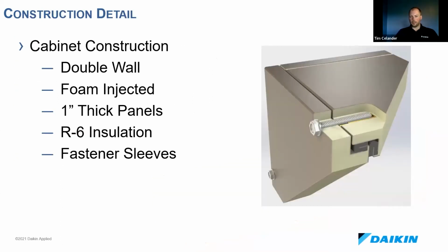So when I talk about that exciting cabinet, here's what I mean. You can see the double wall, that foam injected R6 insulation. Those two black gaskets are what give us that true thermal break, so there's no through sheet metal. And one other thing I'd like to point out is the sleeve that the fasteners go into prevents any stripping as you're removing and reinstalling those sheet metal panels. You can take them off as often as you want without risking any stripping of the sheet metal.